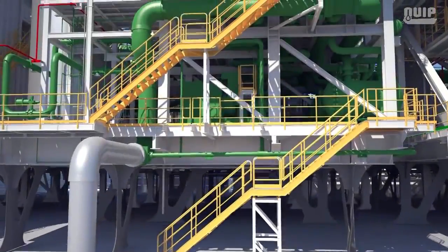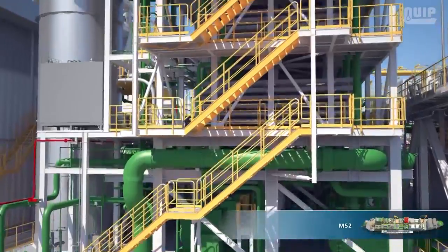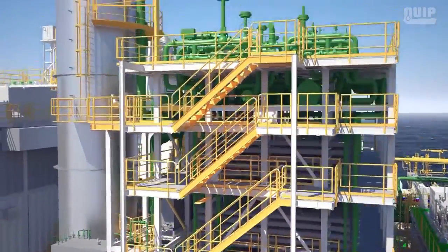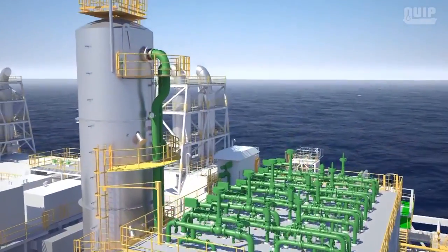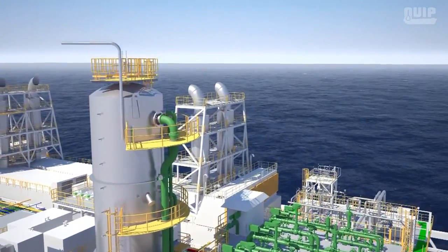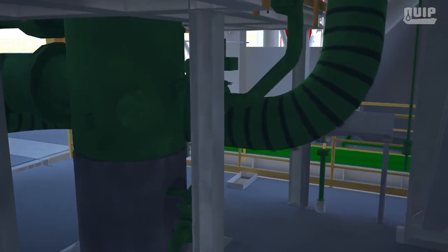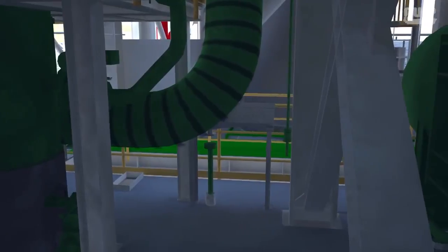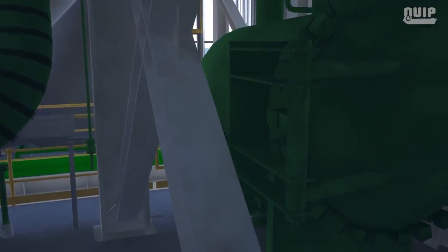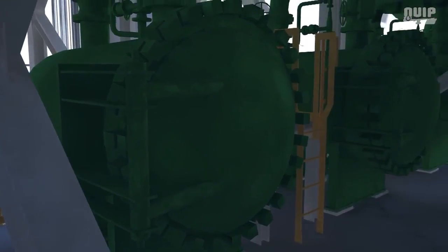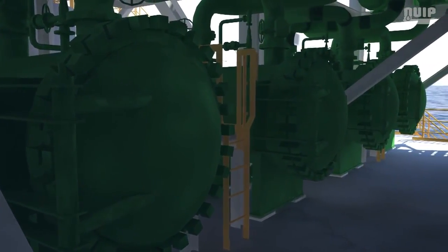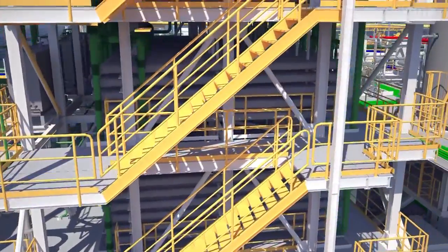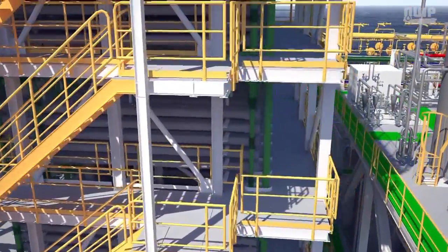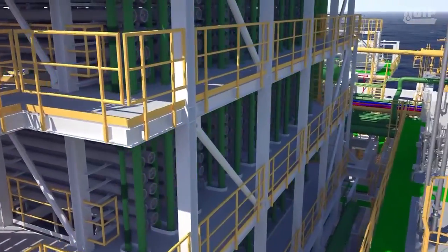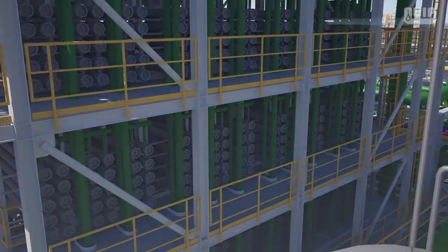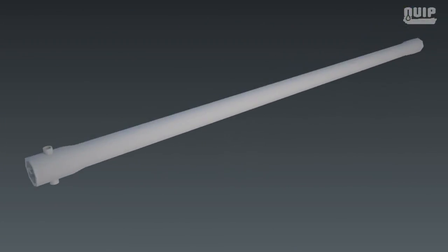The seawater used for utility purposes on FPSO P63 is pumped into the platform's sulfate reduction unit, SRU, through pumps in the hull. The sulfate reduction unit reduces the sulfate level in the water. Initially, the water goes through 3 filtering stages. First, to remove large particles that are more than 80 microns, and then to remove finer particles of 5 absolute microns. After filtering, the water is pumped to be processed twice in nanofiltration membranes, through which the water is forced to reduce its sulfate content.